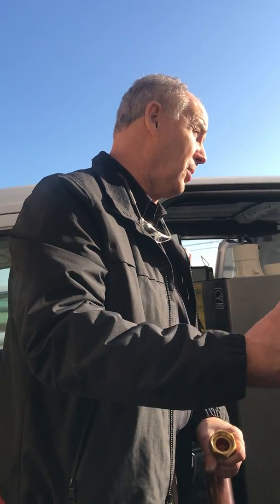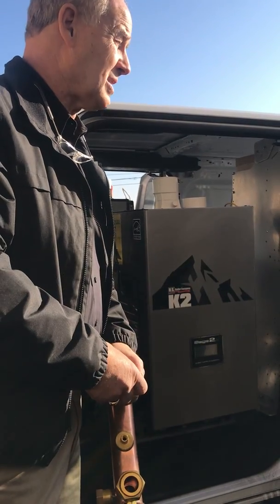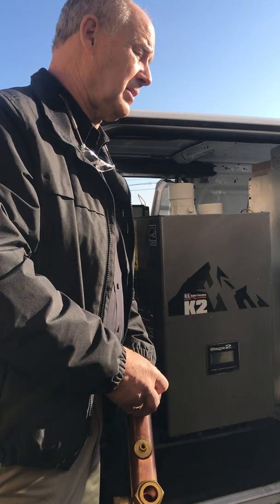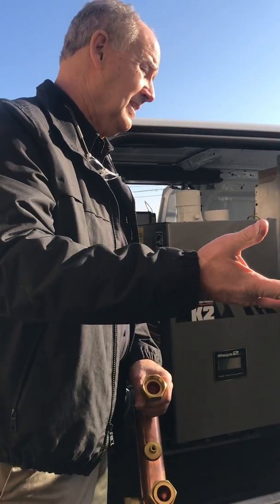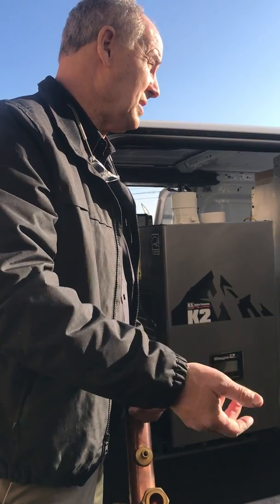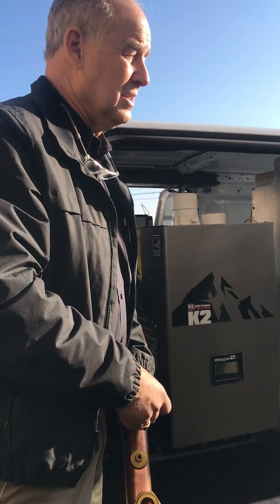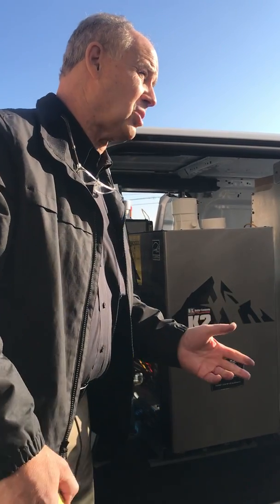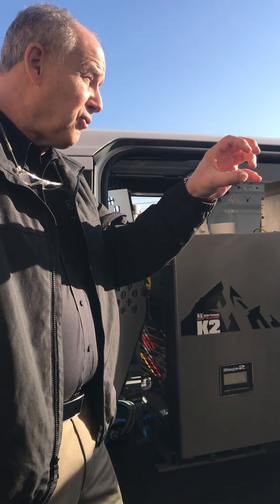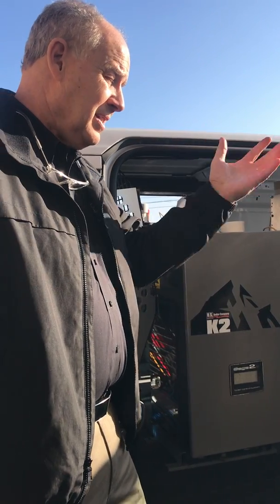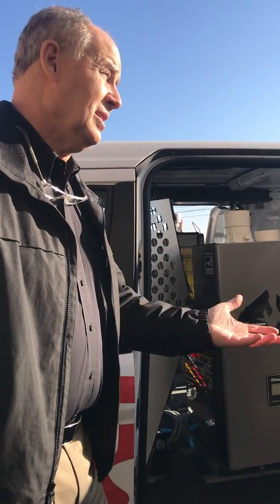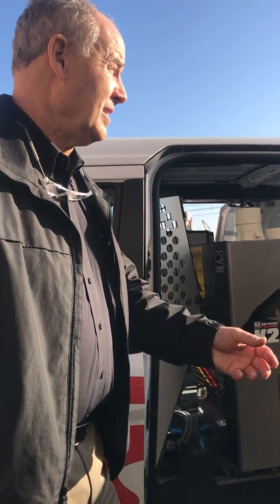Are you supposed to blow it down once a week? Well, you should when you first put it in. You want to blow it down. If you have a float low water cutoff, more and more people are going to the probe low water cutoffs. So it's kind of tough, and people like the probes, but the only thing with the probes, there's nothing to blow down except you can drain. You can't get the surface stuff off. So when you do the floats, if they don't service it, and then you get mud around the float, the float low water cutoff senses that there's water, and it doesn't shut down.